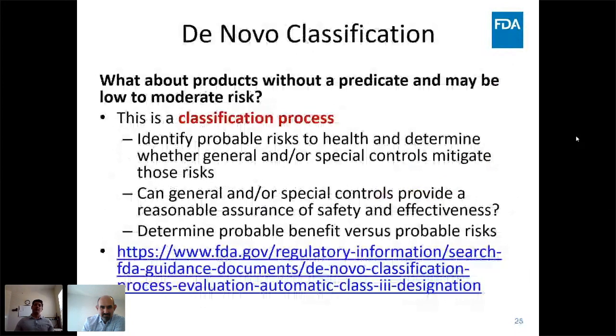So what happens if your device does not have a predicate in the market, but you think it is low to moderate risk? Then there is another classification that we call De Novo classification. In this classification, you have to show that the probable risk to health for the device is less than the probable benefit of the device. Basically, you have to provide special controls in addition to the general controls, and you say that the probable benefits of the device are larger than the probable risk.